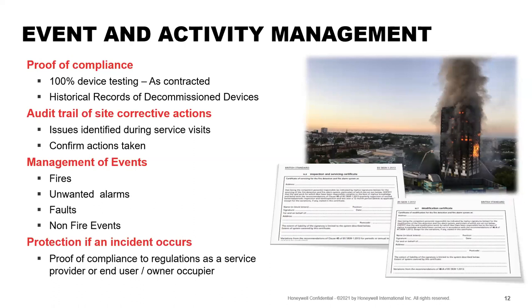So faults, we need to be flagging faults up immediately. You don't need to be waiting until someone walks past the panel to hear it beeping. It needs to flag on the system immediately. So if the end user and the maintenance company are getting an immediate alert on their phone, on a laptop, on a desktop, they can be much quicker to respond to that, to get back to the system being 100% compliant as fast as they can.